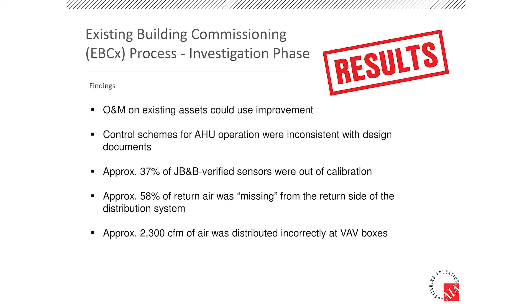Control schemes for the air handling units had changed drastically over time when we went back and looked at it, which is somewhat typical for an existing building, especially one that's been in operation a long time — this system for 8 years. You make a tweak here, change something there on account of a hot-cold call, and next thing you know your variable air volume system is a constant volume system, and you're changing discharge air temperature all the time. It happens, right? So we worked with the BMS guy to get some of those control schemes back to where they needed to be for design.